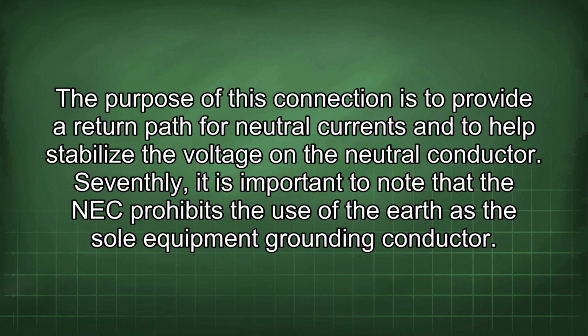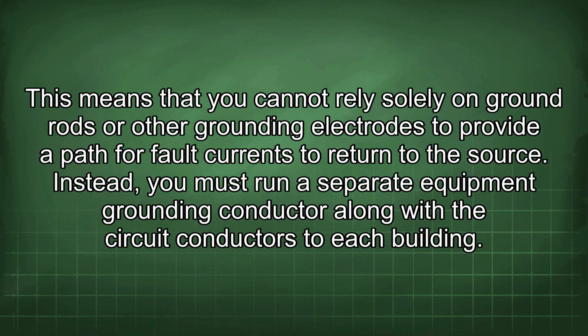Seventhly, it is important to note that the NEC prohibits the use of the earth as the sole equipment grounding conductor. This means that you cannot rely solely on ground rods or other grounding electrodes to provide a path for fault currents to return to the source.